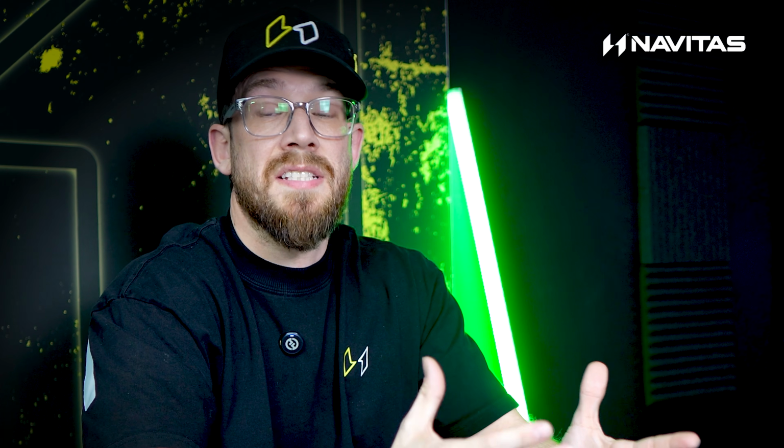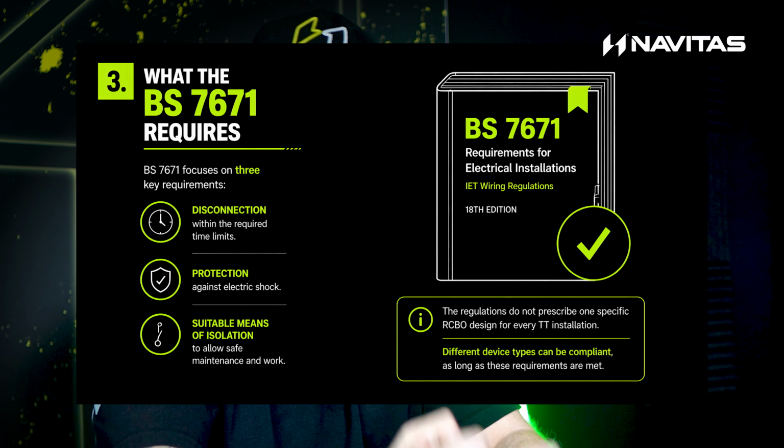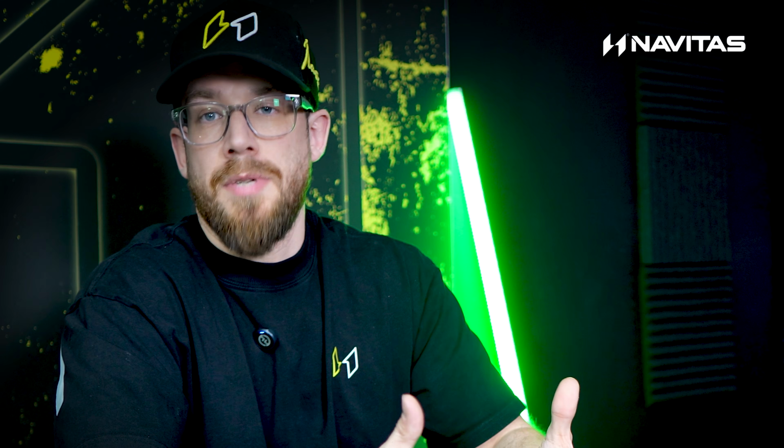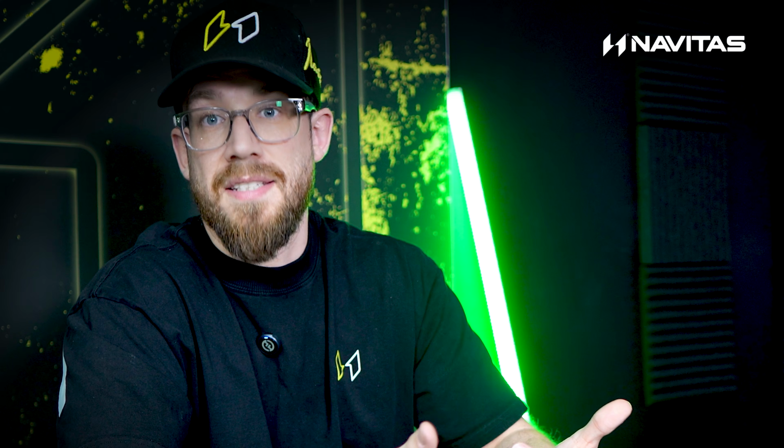So BS 7671 is looking for three key points: disconnection time within the required times set, protection against electric shocks, and a suitable means of isolation. What they don't do is tell you which RCBO to use for every specific TT installation. So there's flexibility in how those systems can be designed, providing those three key points are met.